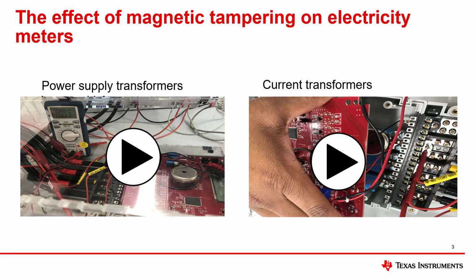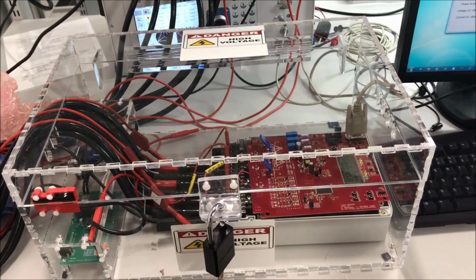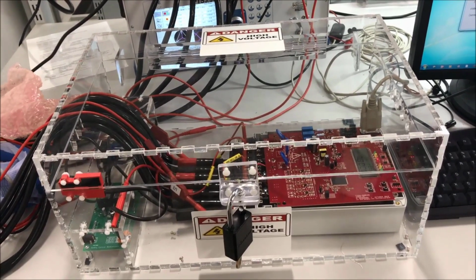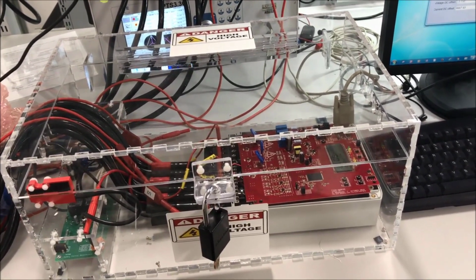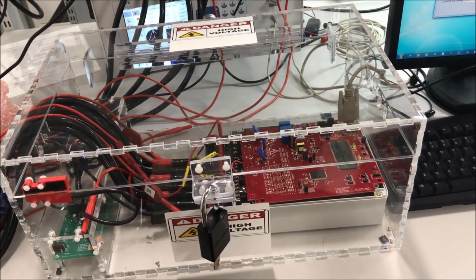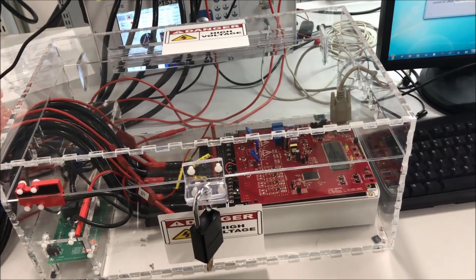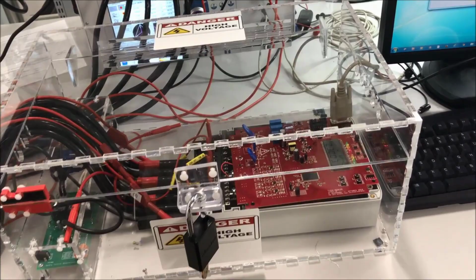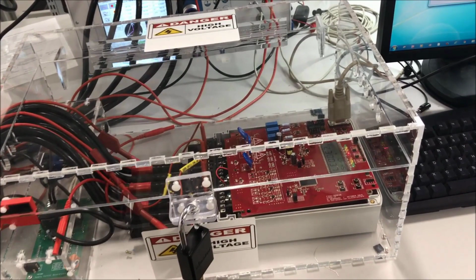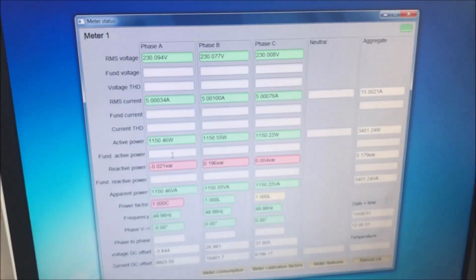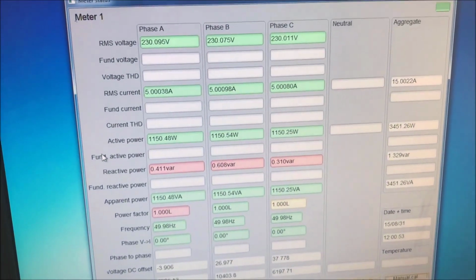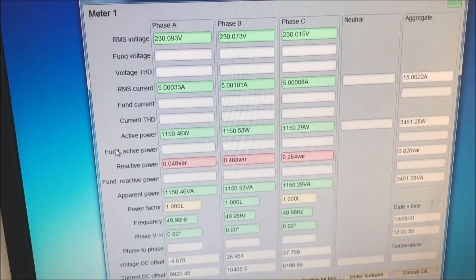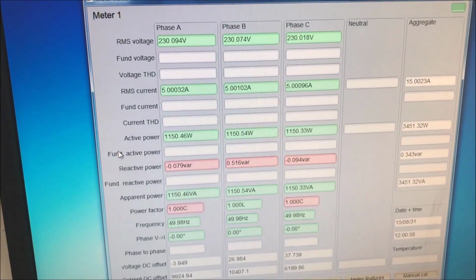Strong magnets can also affect current transformer current sensors. To show the effect of magnetic tampering, we apply 230 volts, 5 amps, a unity power factor on each phase of electricity meter. To show the effects of tampering, we use a PC GUI that will display the active power readings of each phase. Here we see that approximately 1150 watts has been applied to each individual phase.